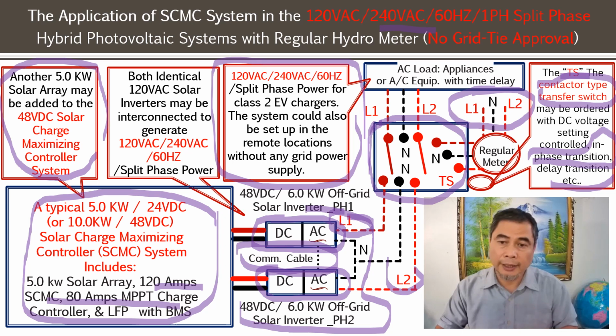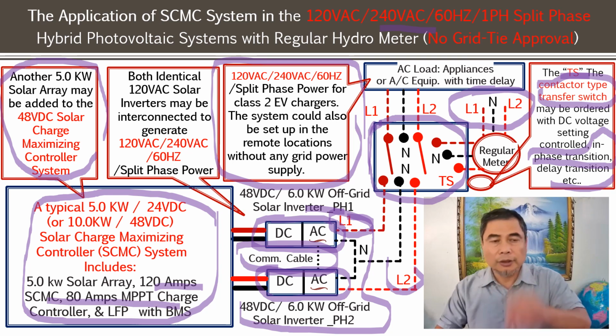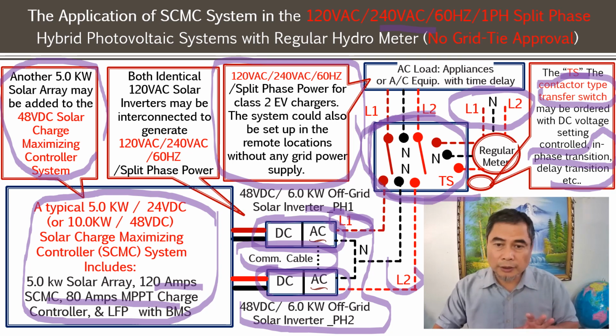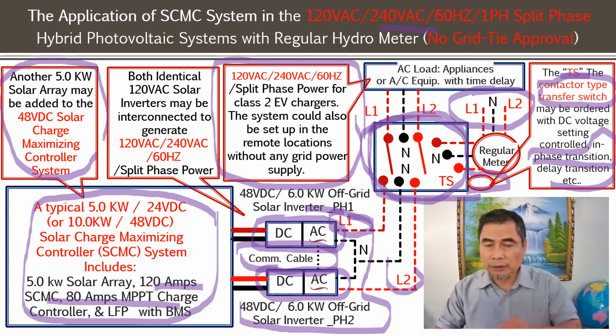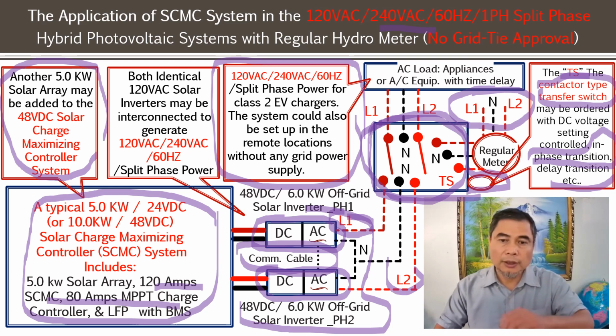So this is an idea that can make it happen very easily to maximize the off-grid or grid-tied system. So I'm sorry, it's not a grid-tied system, it's an off-grid, a hybrid system but with no grid tie. So this is the nature of what we are talking about. However, this is the transfer switch, a relay type of transfer switch, not the automatic transfer switch. You can buy it directly, but it has to be ordered from a certain manufacturer.